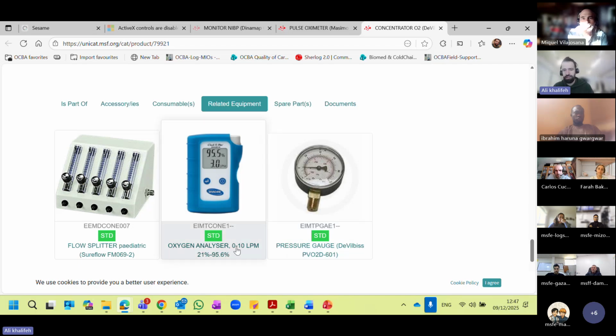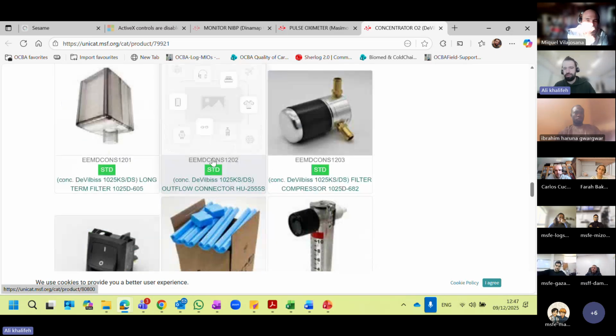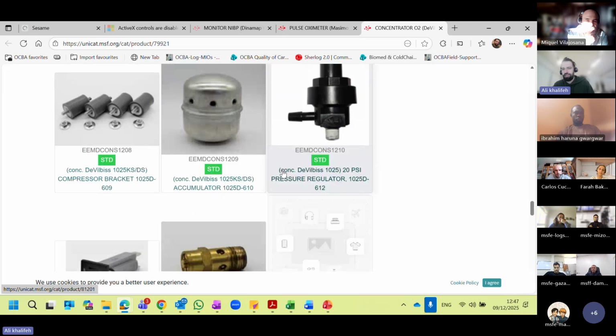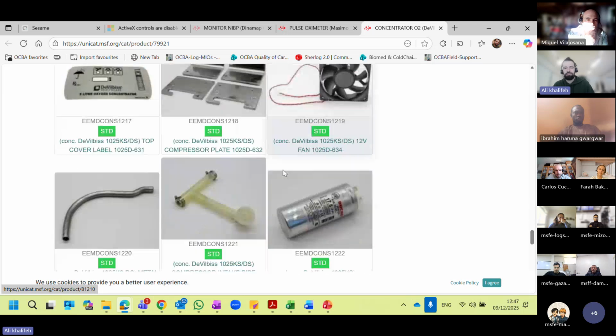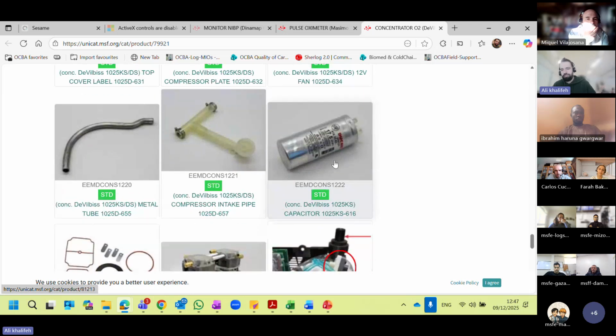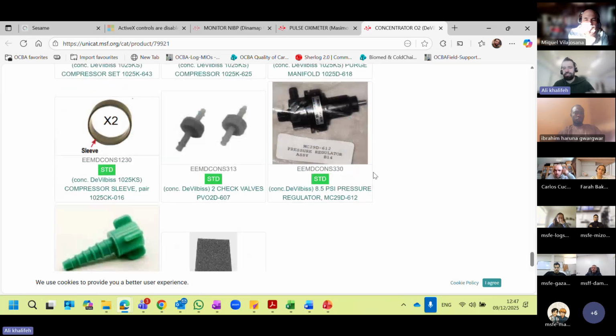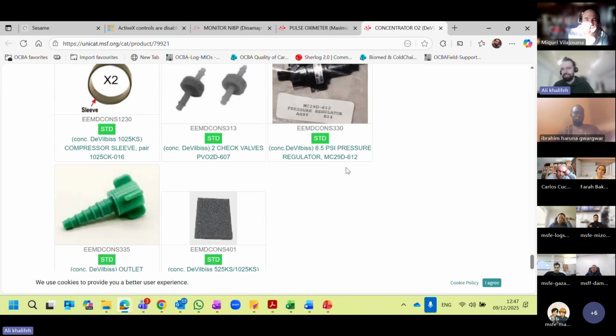For example, we have the oxygen analyzer that measures the oxygen percentage given, or the outlet oxygen concentration for this concentrator, and the manometer for some internal tests. So it's very important for me as biomedical to order these too for the maintenance. Spare parts, we have all the spare parts. Some of them we already requested, but for example, I can see here that we have some capacitor, maybe it's needed, otherwise, so I do a quick review on this list. We always advise people to go to Unicat. Tamam, is it clear how I did the request?